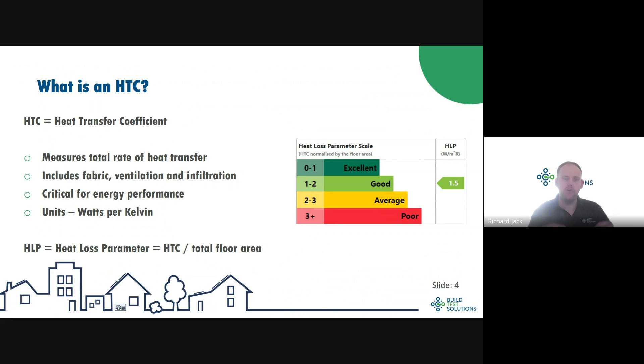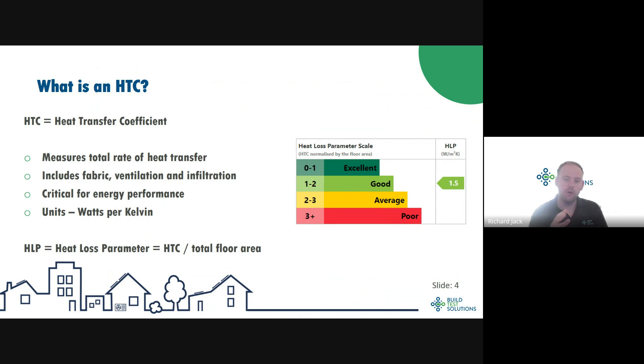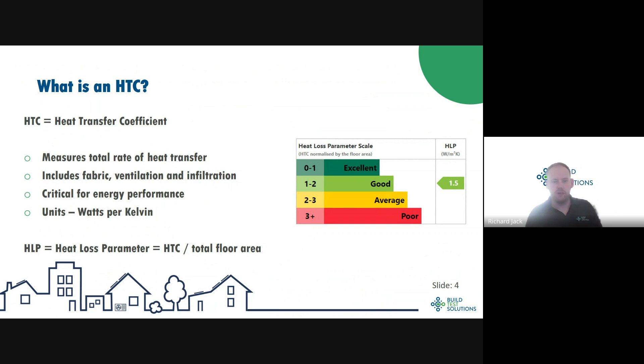The HTC is a measurement of that total rate of heat transfer and it's completely critical for your energy performance. If you have good thermal performance you need less energy to keep it warm inside and the energy consumption of the building will be lower. The units of the heat transfer coefficient are watts per Kelvin — watts referring to a rate of energy transfer (joules per second), and per Kelvin referring to the temperature difference between inside and outside.